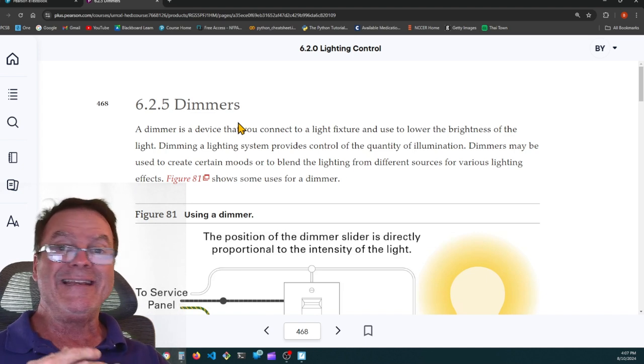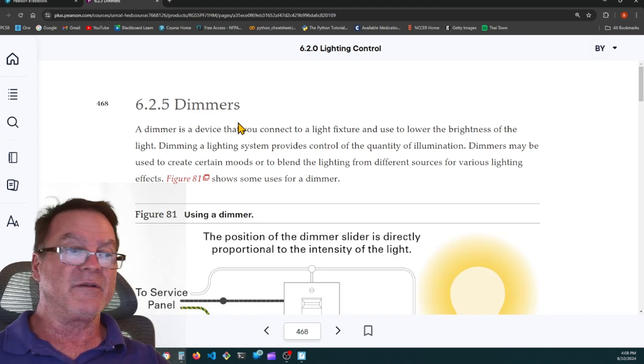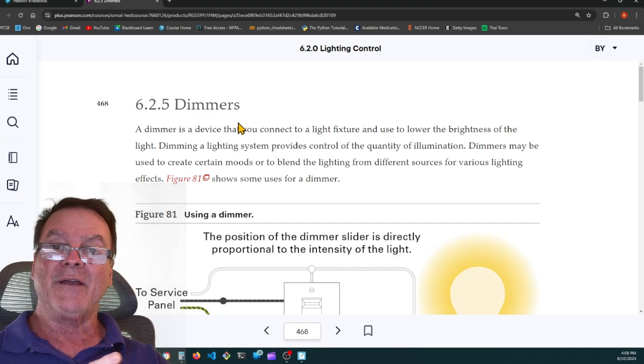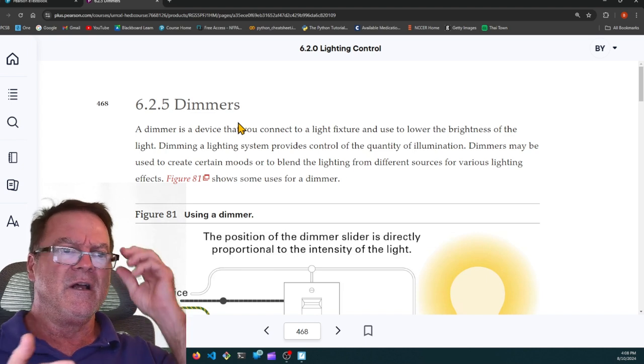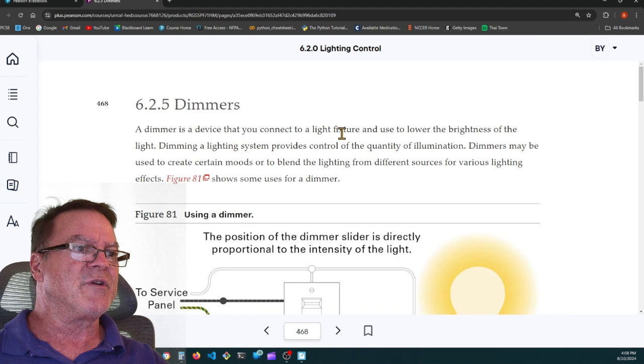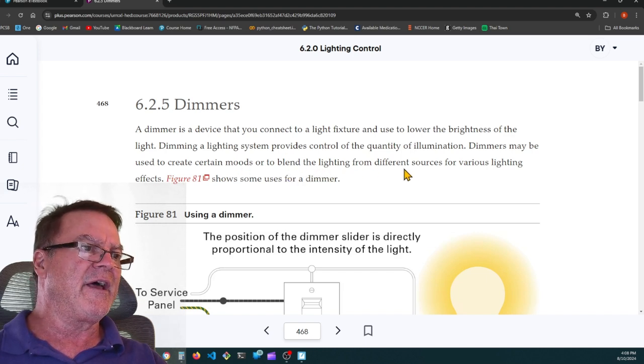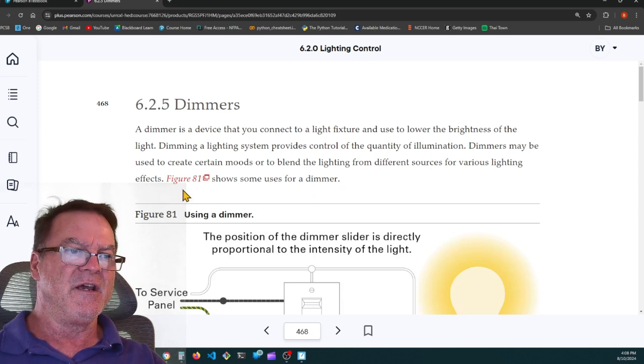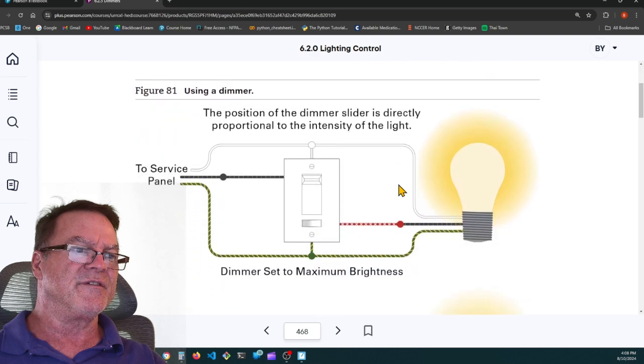Nowadays we have LED, we have compact fluorescent, we have incandescent, and they sell dimmers at Home Depot that handle all of them. It says right on it, good for incandescent, LED, CFL. They can dim anything. A dimmer is a device that you connect to a lighting fixture to use to lower the brightness of the light. Dimming a lighting system provides control of the quantity of illumination. Dimmers may be used to create certain modes or moods, or to blend the lighting from different sources for various lighting effects. Figure 81 shows some of the uses of a dimmer.